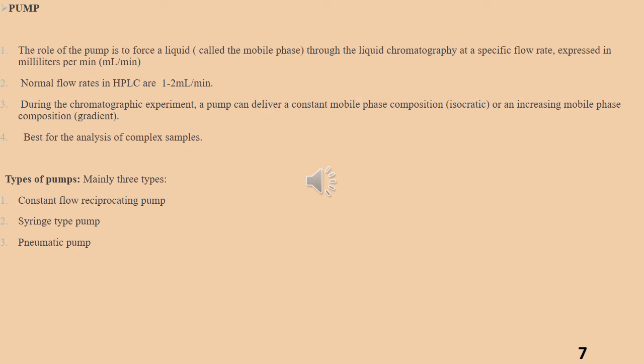The pump head is equipped with check valves to ensure the positive direction of flow. The main difference between the reciprocating pump and the syringe pump is based on the higher piston frequency and the smaller volume of the solvent delivered during each piston cycle by the former.